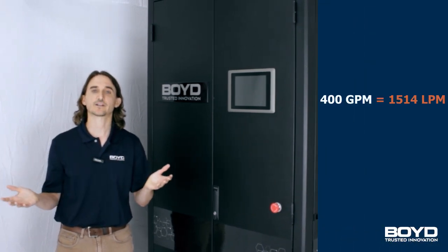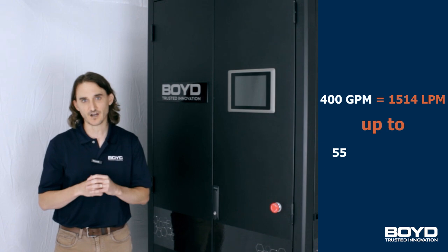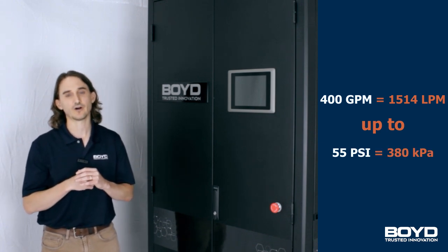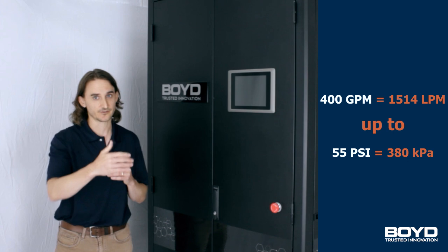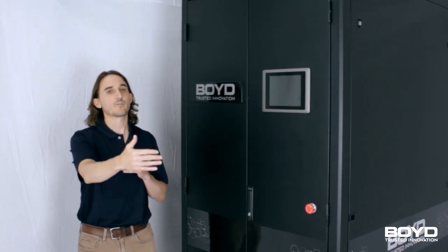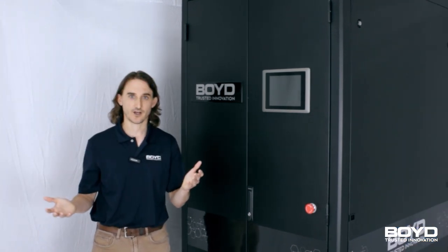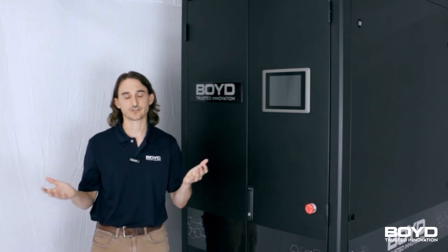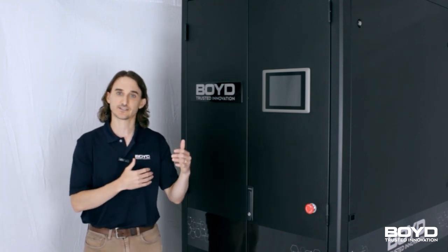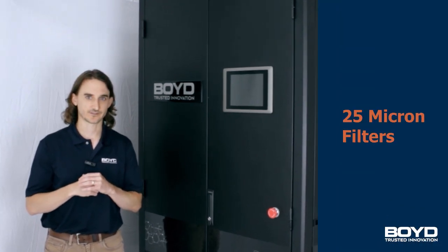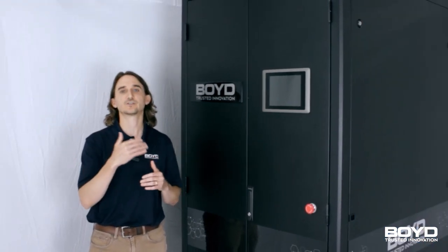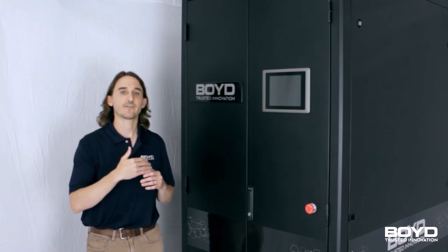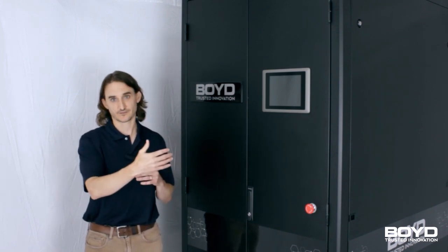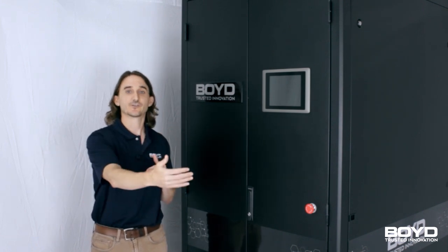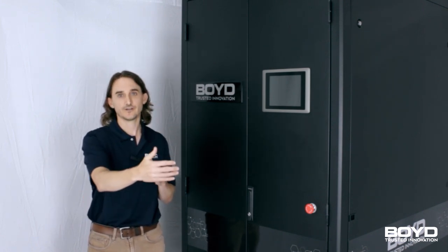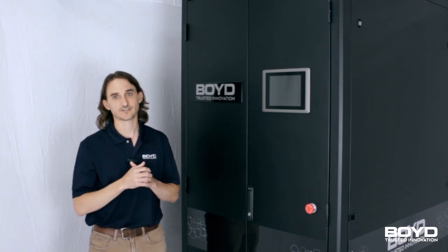We operate at 400 gallons per minute, up to 55 PSI differential allowable at the data center. That's exterior to the unit. This enables a wide variety of cold plate options because of our large pressure differential. That circuit is protected by 25 micron filters. This is very important because we ensure that our system can provide that much pressure with clogged filters, and those filters ensure that the cold plates are receiving clean fluid so that they're not clogged and performance is not hurt.